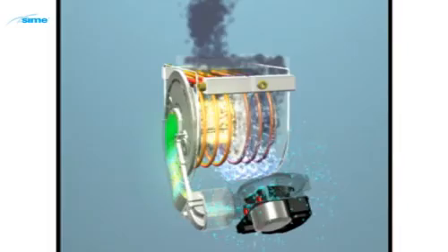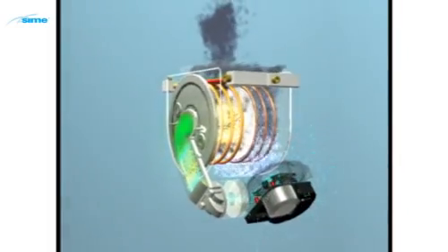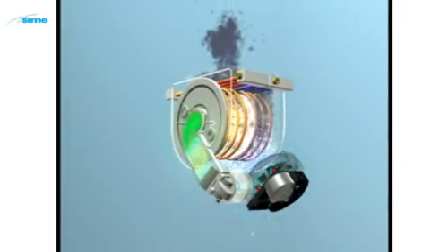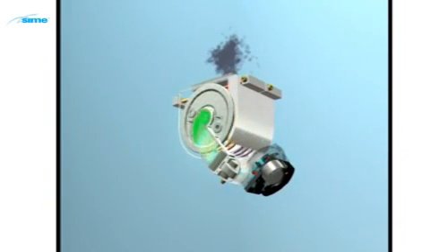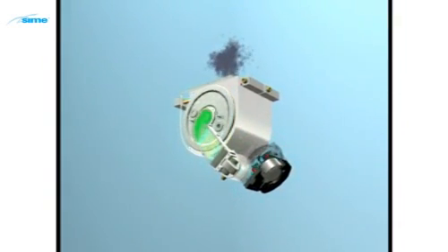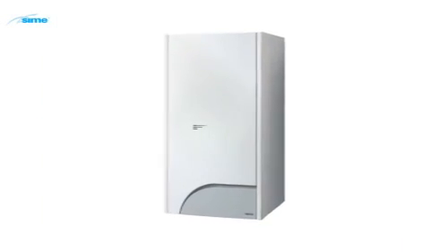Increasing the fan speed increases the output. Precise control of the fan speed is achieved by the use of a stepper motor. Electromagnets hold the fan from turning. The magnets are turned off and on, allowing the fan to turn. The rate at which they switch controls the speed of the fan.